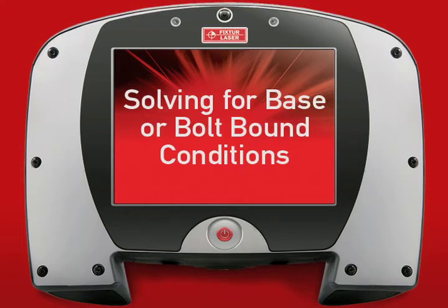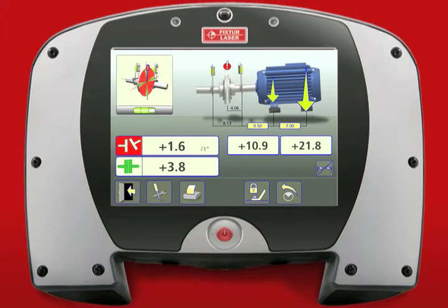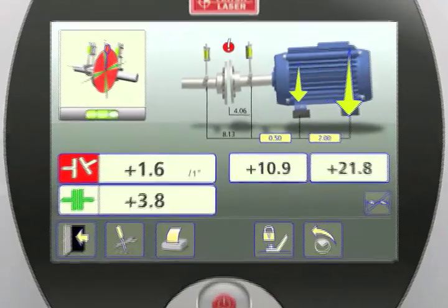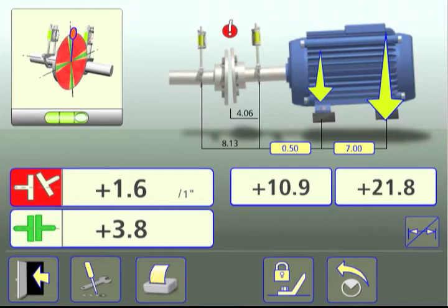Solving for base or bolt-bound conditions. During an alignment, the movable machine's feet may be determined to be base-bound or bolt-bound when there just isn't enough leeway to make the indicated adjustment.